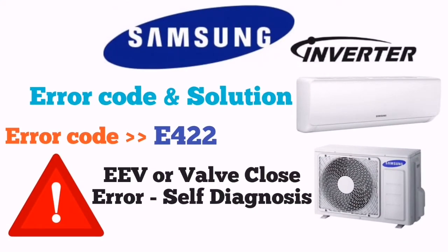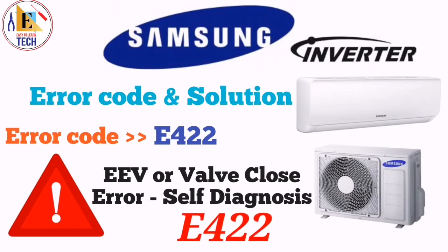When you see an error E422, or your LED 1 is on, LED 2 is on and LED 3 is off, it means it's an EEV or valve close error, self-diagnostic. First of all, you have to check these 4 points. Check the position of the indoor EVA in sensor, whether it is normal or not. If it is not in the normal place, place it in the normal place. Then check the pipe for cracks. Then check in your outdoor whether the EEV valve is connected properly or not. And then at last check whether the refrigerant was charged properly or not.